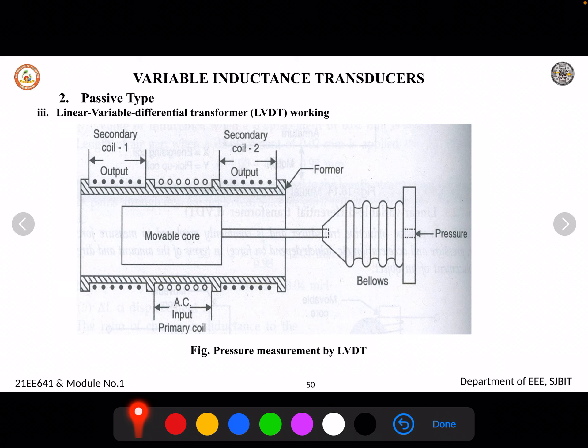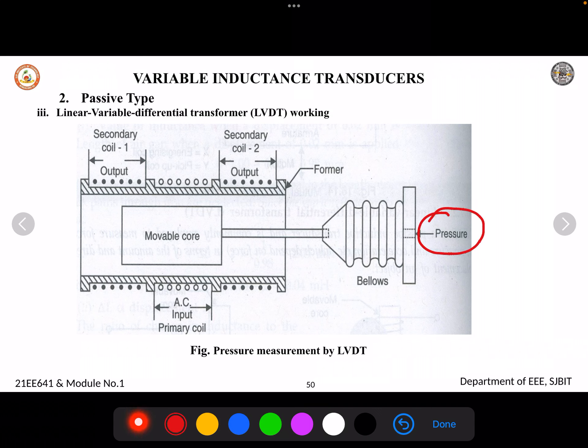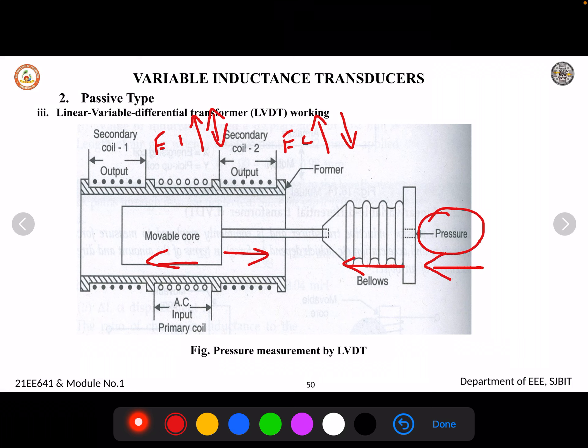This second diagram shows another LVDT device with a primary coil, two secondary coils, and a movable core. Here, bellows are used to move the core — pressure is applied to the bellows, causing compression or tension, which moves the core forward or backward. Based on the direction of movement, E1 and E2 increase or decrease, and the output voltage is measured accordingly.